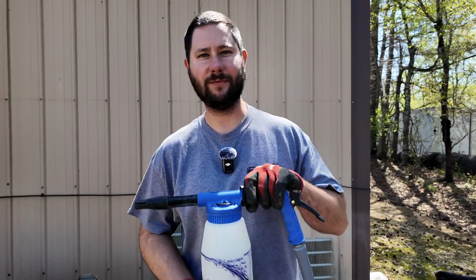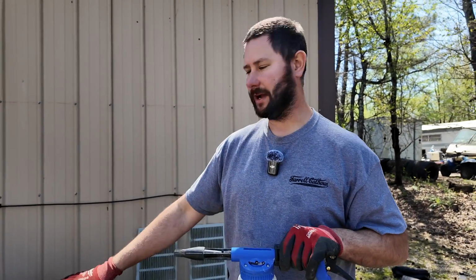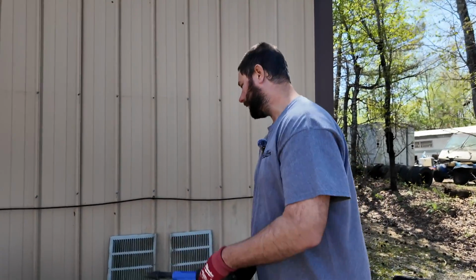We got our coil gun filled with coil cleaner. Now we're going to start to clean the coils. I want to tell you that if you only clean the coils, but you don't clean the grills or the top, and it still looks like it's dirty, the customer's going to think you didn't clean it. So make sure that you spray off the top and you get a rag and you wipe it, and then you spray off these grills.